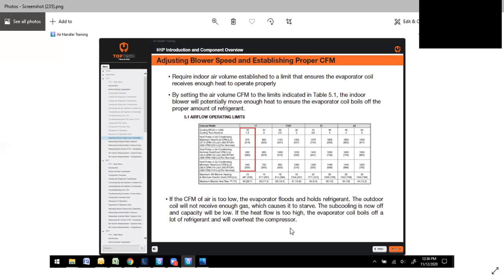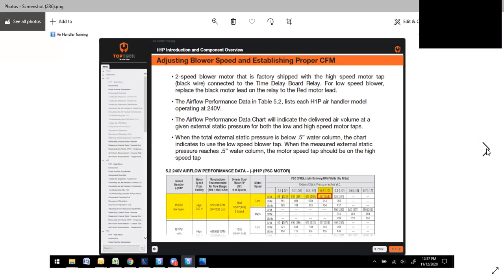We'll dig into this a little bit, but airflow is very critical. That will affect your charge on the heat pump side or air conditioning side as well. It'll affect the comfort. It will affect everything. When you're adjusting blower speeds on the EC or PSC, the 2-speed blower motor that is factory shipped is already set for the high speed.